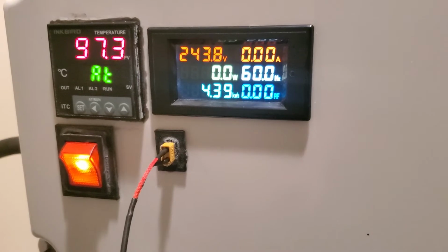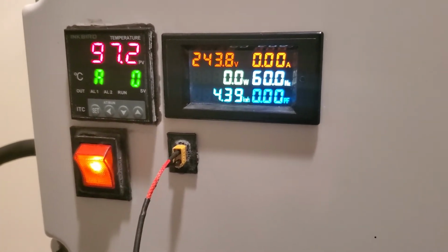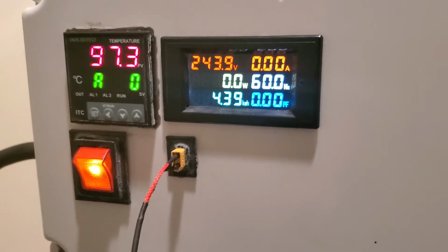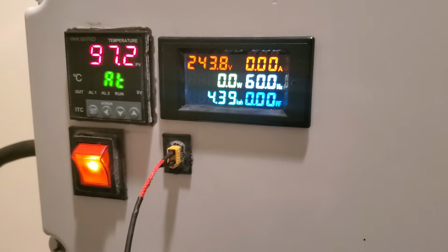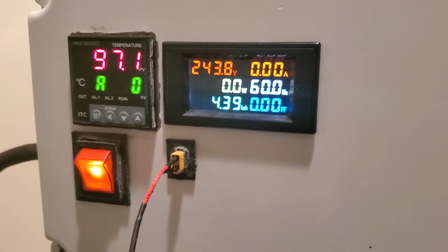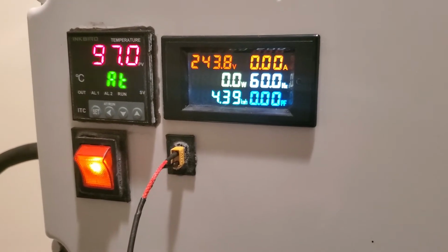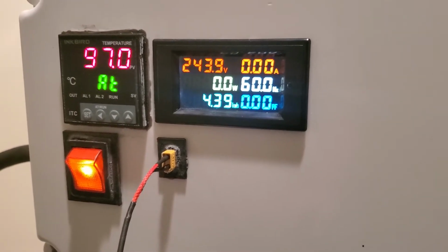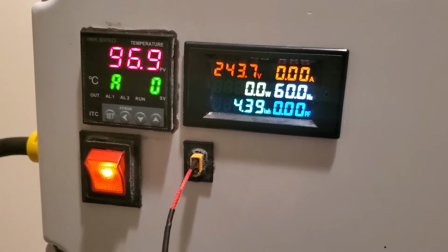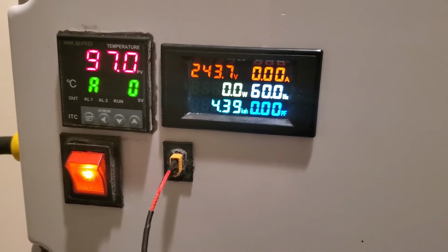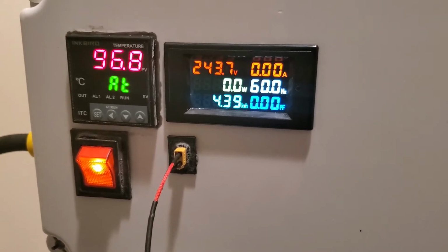One other thing that isn't mentioned in the documentation: the auto calibration mode can take a long time depending on the process you are trying to control. So if you have something that changes temperature quickly, this can be a relatively quick process. But if you have something that has a large lag in temperature, for example mine, I'm heating a large amount of liquid, this auto calibration or auto tuning process can actually take quite a long time to complete.